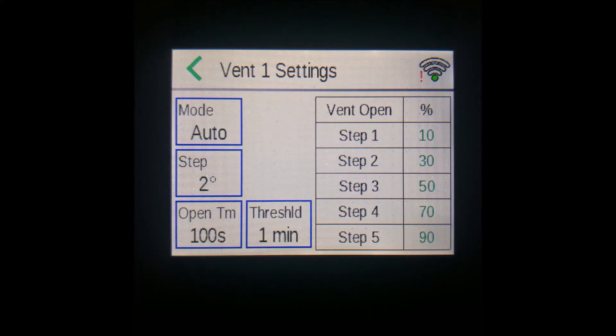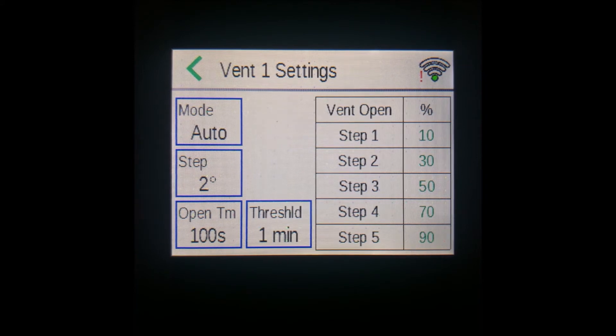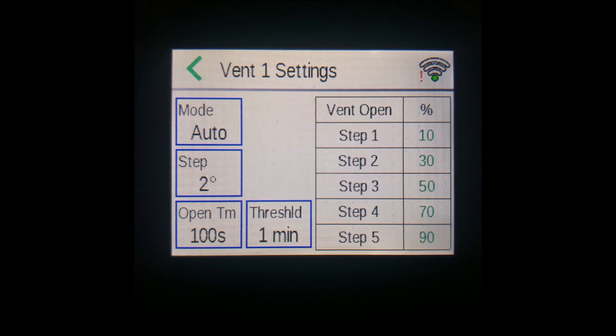The vent's function is to keep temperature at the target temperature by opening your vents to a percentage specified by you for each step above the target temperature. If you have your step value set at 2 degrees, for each 2 degrees above the target temperature that the current temperature is, the controller will open your vent one step.